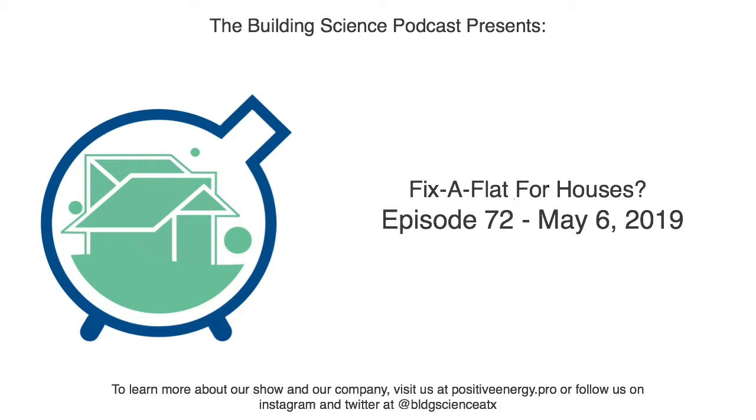And just a tiny bit more, this is my personal curiosity. I'm trying to imagine the edge of a gap, and I have this molecule that has impinged on the edge of the gap, and it grips. Then the next molecule hits it, and these molecules are coming at a high velocity, so they're small, but there's momentum. It seems like they could rip off the grip of the first molecule, and the material itself could be friable. Well, you just keep coming at it with soldier after soldier. That is where the technology is: we make a sealant material and control the particle size, the air velocity, all that. It's sticky enough, it has enough chemical adhesion. The material dries non-sticky, and when you see it, it's almost like a bead of caulk.